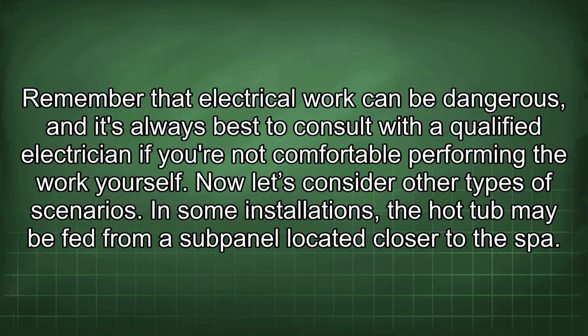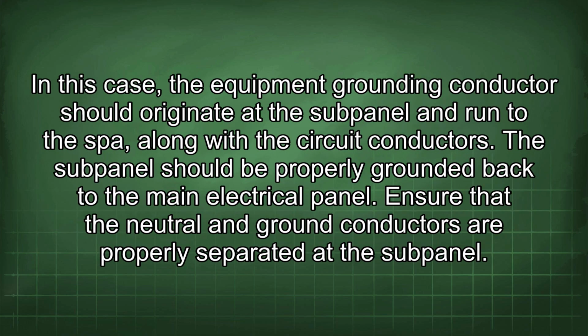Now let's consider other types of scenarios. In some installations, the hot tub may be fed from a sub-panel located closer to the spa. In this case, the equipment grounding conductor should originate at the sub-panel and run to the spa, along with the circuit conductors. The sub-panel should be properly grounded back to the main electrical panel. Ensure that the neutral and ground conductors are properly separated at the sub-panel.